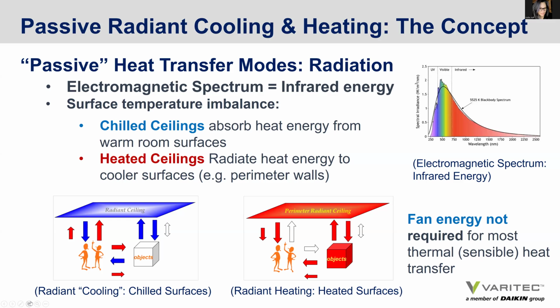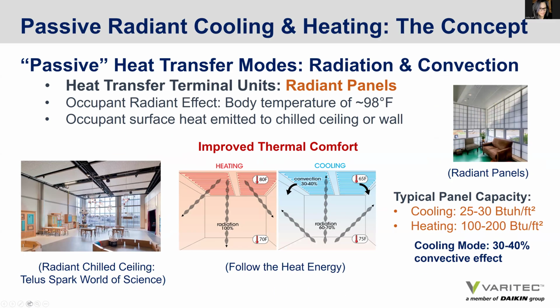So heat transfer in a zone that is using the radiant effect requires less fan energy to move the energy from that space. There are different types of radiant devices that can be used. There are radiant panels. If you cool that radiant panel to 58 to 60 degrees, it'll absorb any of the energy present on any warmer surface, giving a cooling effect. And if any of you have had the opportunity to stand before maybe the mouth of a large cave where it's cooler, you feel cooler because the radiant energy that your body is giving off is absorbed and relieved from the environment of your presence. So you have that cooling effect, which offers a thermal comfort component.